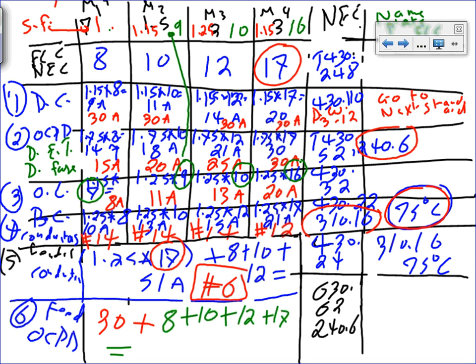Eric, my friend, what are you doing here? You're supposed to be my calculator, man. This is the 17, we'll have a 30. You take the largest overcurrent protection device of the system, and you add to it the full load current of all the others: 8, 10 plus 12. You don't add the 17. You're absolutely right, because the 17 is covered by the overcurrent protection device of it.